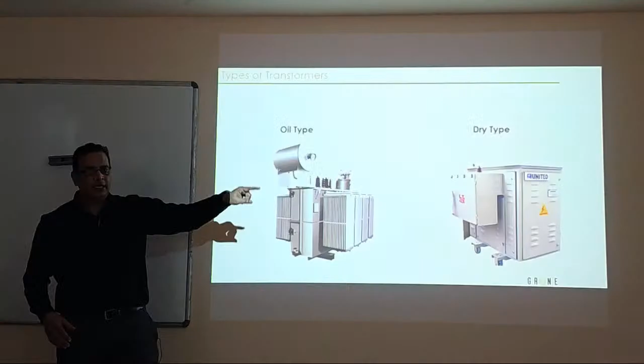It should have open ground outside because it has oil to cool the system. If there is oil within this, it is an explosive material, and if that explodes, it is going to impact the building also. That's the reason why the regulation says you have to place them outside. So when you place electrical transformers within the building, we use dry type. The dry type transformers go within the building. Some examples of the pluses and minuses of oil and dry type, I'll skip this, it's not a necessity for you.